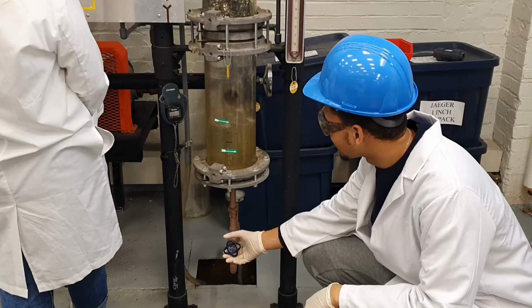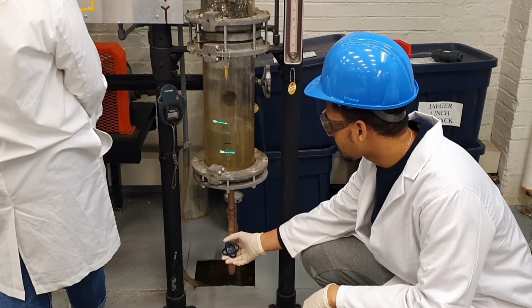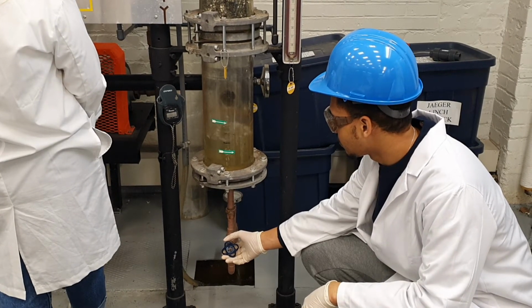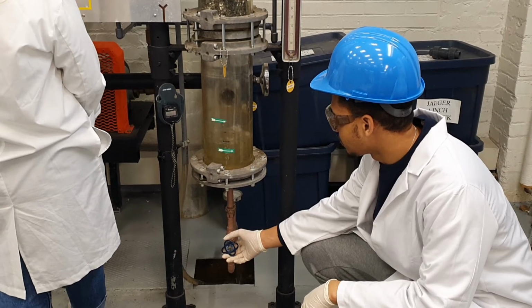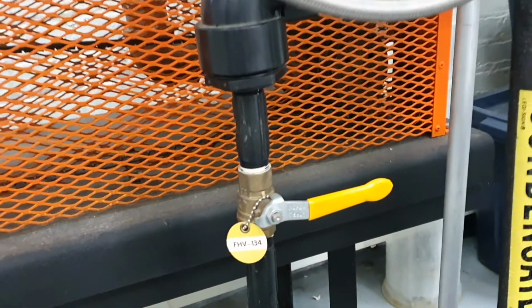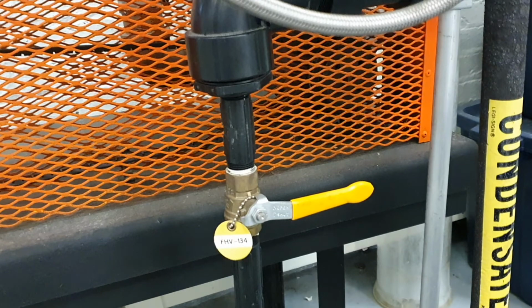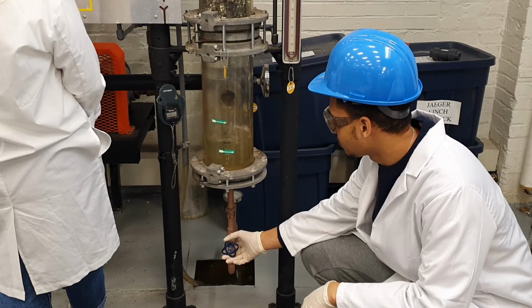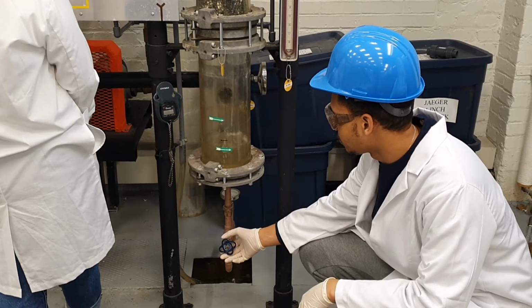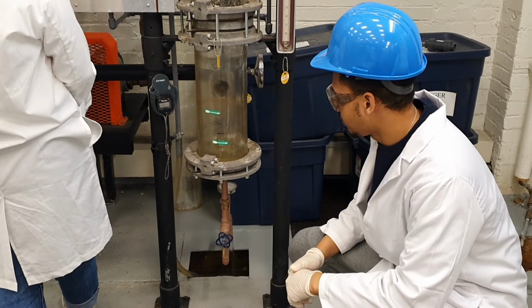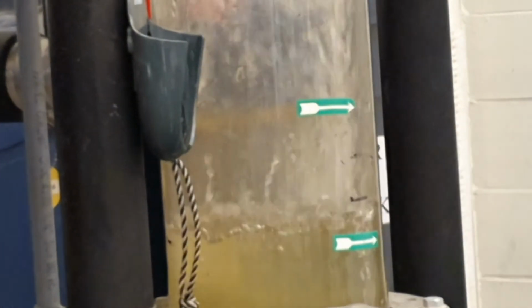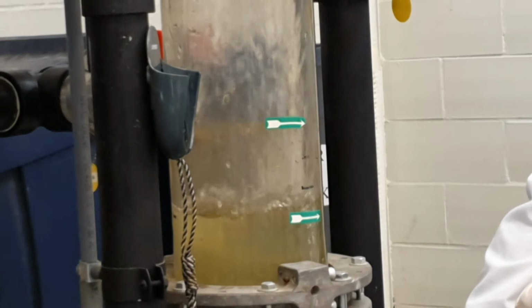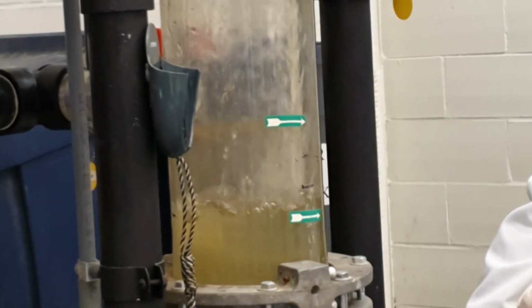There are a few additional safety concerns associated with the gas absorber operation. First, if the water level exiting the column goes above the top green arrow placed on the column, open valve FHV 134 immediately. Additionally, ensure that FHV 148 is open completely. This will prevent water from entering the heat exchanger and compressor. Leave FHV 134 open until the water level exiting the column is below the top green arrow.